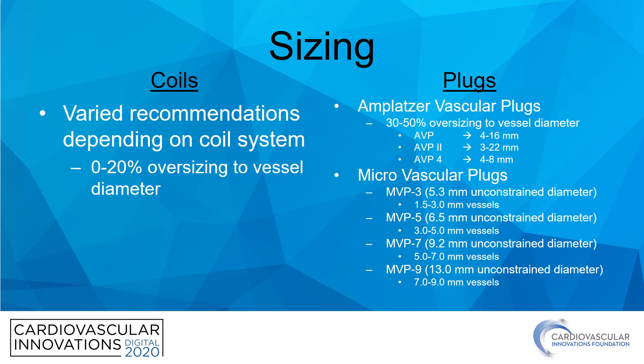For AVPs, the general recommendation is oversizing the device by 30 to 50 percent of the vessel diameter. MVPs are a little different — each of the four available sizes (3, 5, 7, and 9) has a range of vessel diameters recommended for use. Oversizing is always preferred. For example, if you have a vessel that measures 3.0 millimeters in diameter, using an MVP-5 would be preferable.